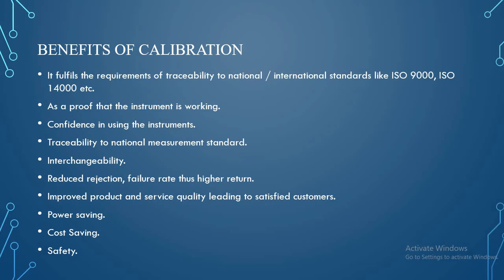The next benefit is as a proof that the instrument is working. So when we go for the calibration, first the instrument should be in working condition. Otherwise, the calibration cannot happen. So when we say the particular instrument is calibrated, it means we are assuring its working condition.